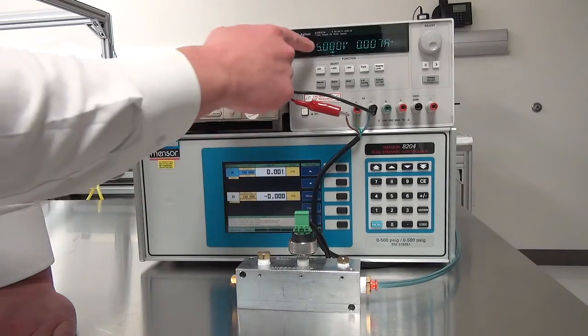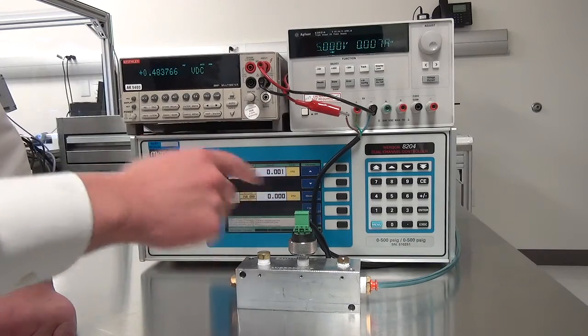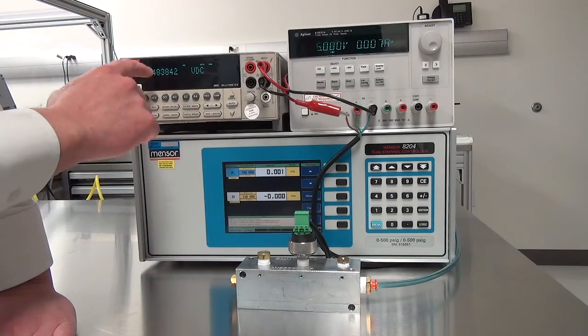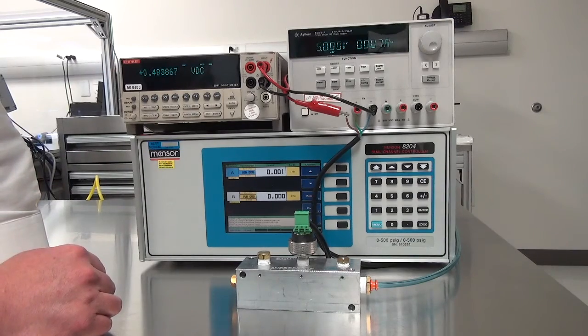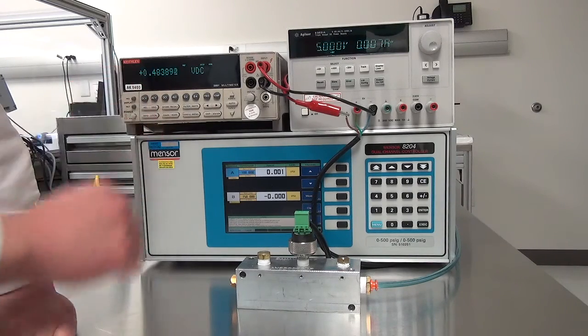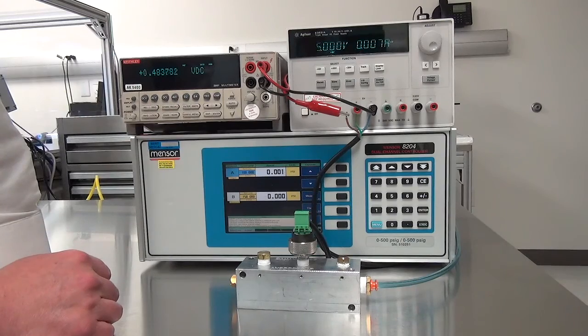You can see here that we've got 5 volts going to the sensor supply. Our target output, the calibrated output of 5 volts should be about 0.5 volts. Here we're sitting at 0.483 volts well within specification.